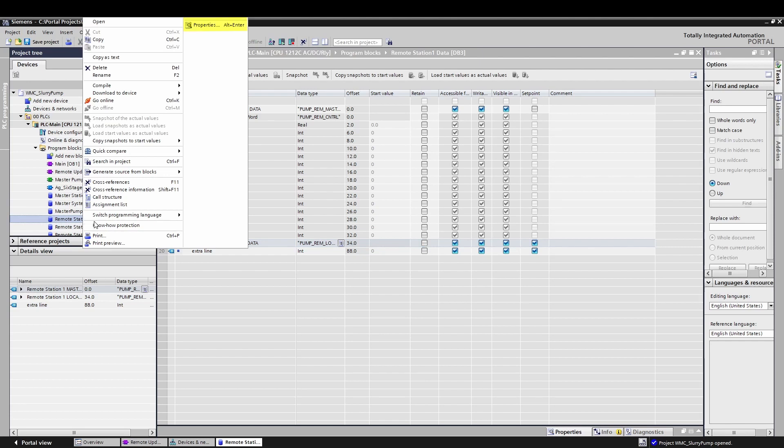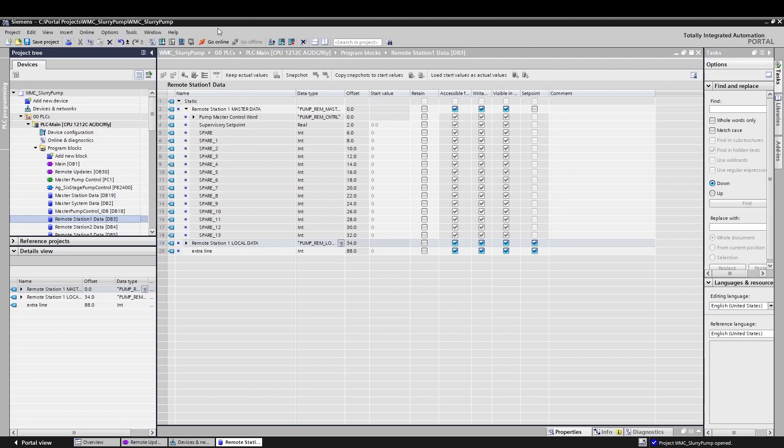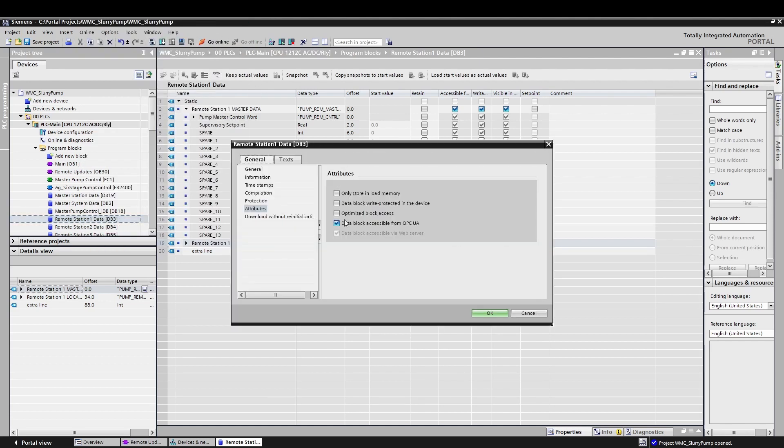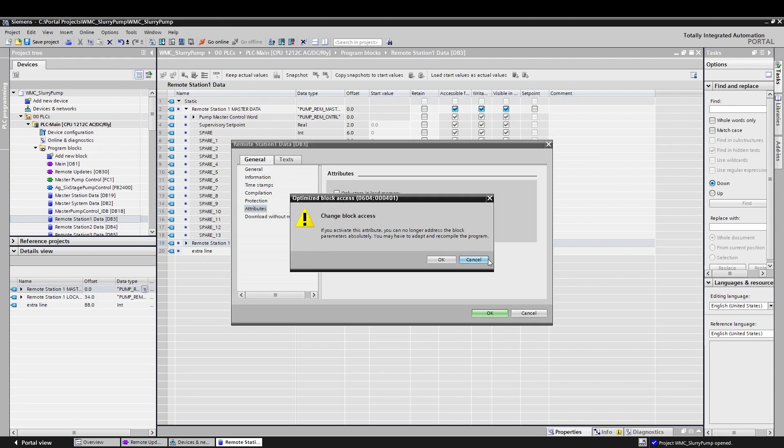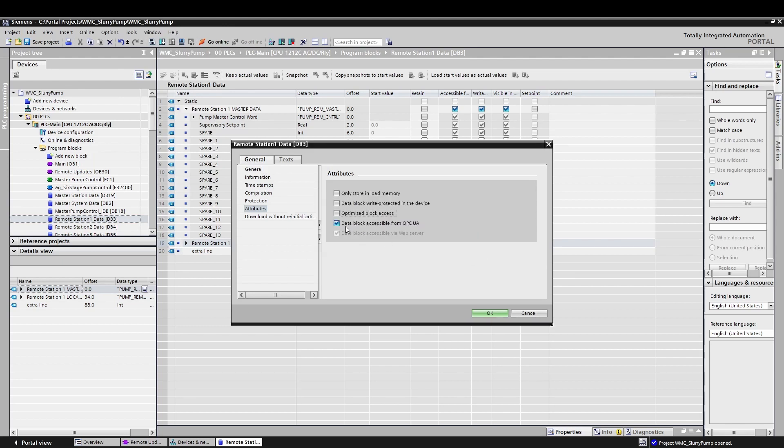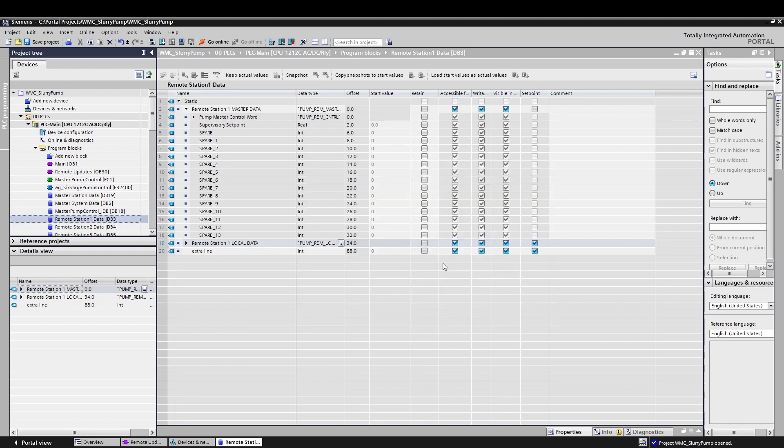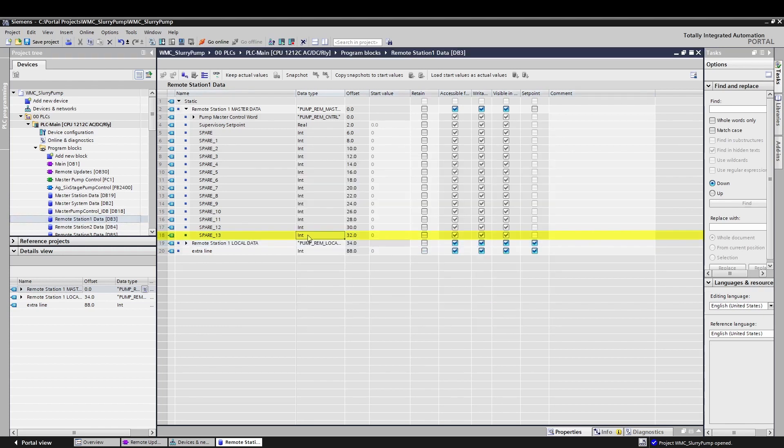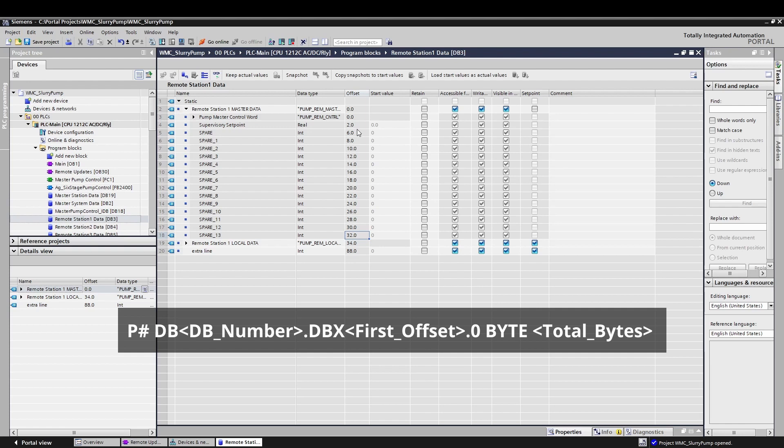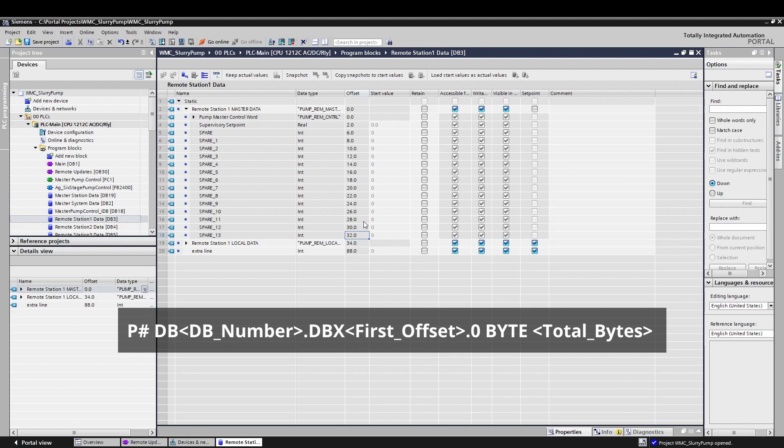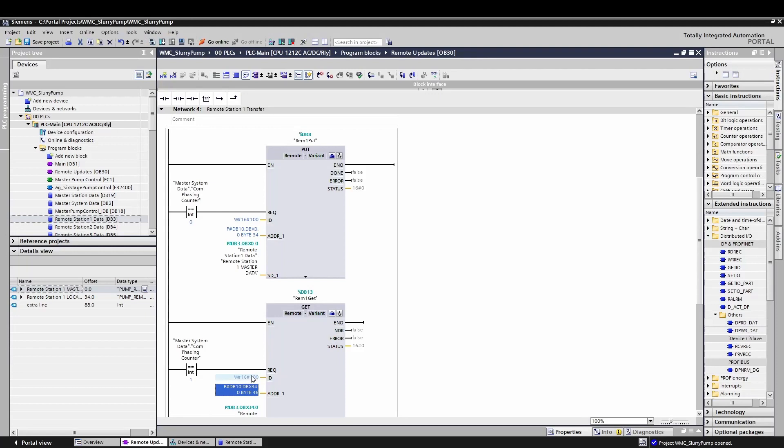By default, these offsets are not shown because these blocks are optimized. To see these offsets, right click on the block and go to properties. Under general, uncheck the box that says optimize block access. You will need to do this for any pointer based function. As you can see, the last tag is an integer that starts at an offset of 32 bytes. To create a record, use the pointer designation as shown. You can easily figure out the total number of bytes by looking at the last offset, then adding how many bytes are in the data type that's represented by that tag. Be aware, this trick only works if you are starting at dbx 0.0.